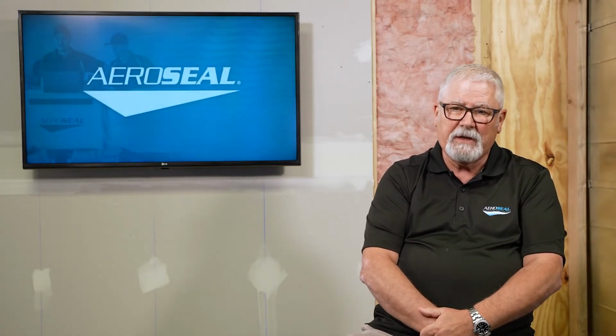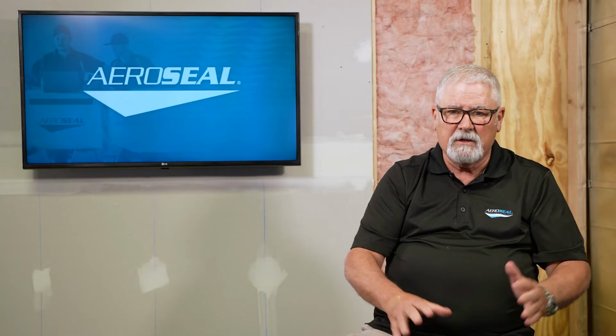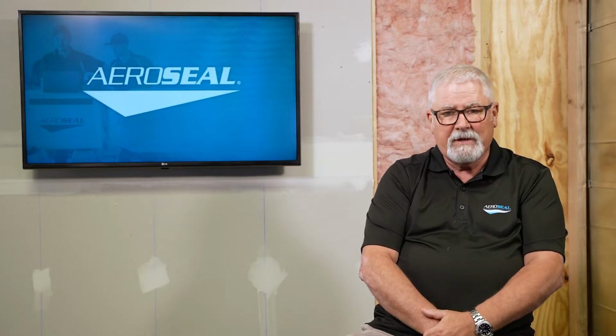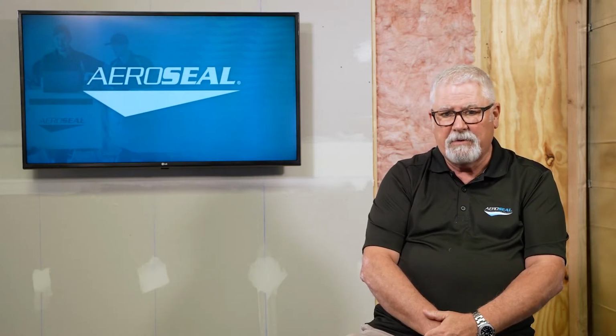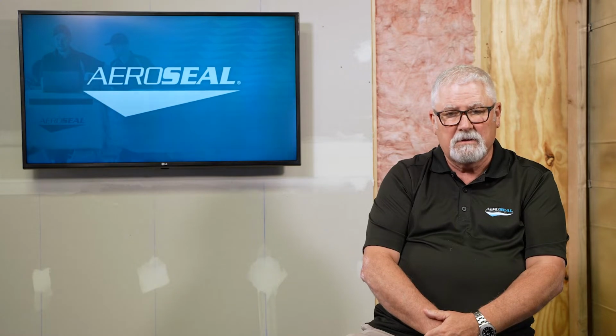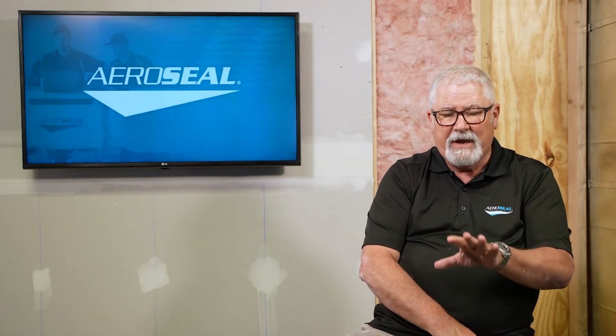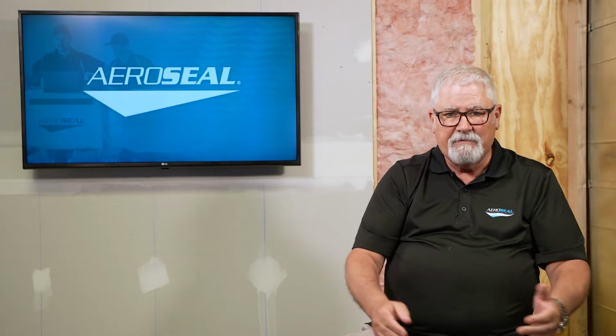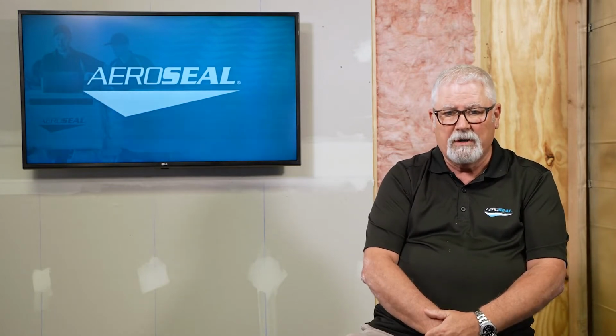The simple answer to all of this is panned joist bays have to be sealed. You cannot leave them unsealed and expect the job to be done properly. In that case, maybe some hand sealing might be needed to help seal up that duct, or maybe replacing it with a ducted return. But you can't walk away from it - you can't leave it unsealed, because that's when problems will arise.